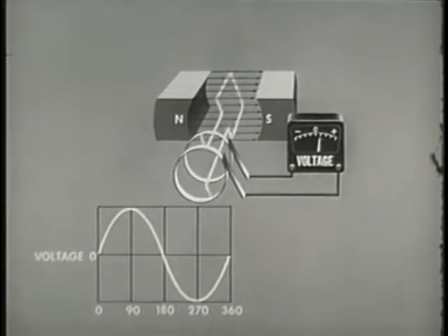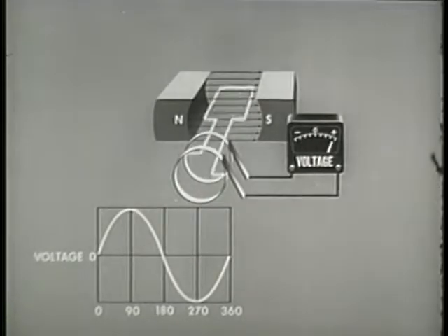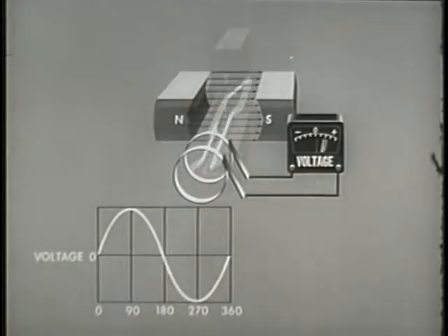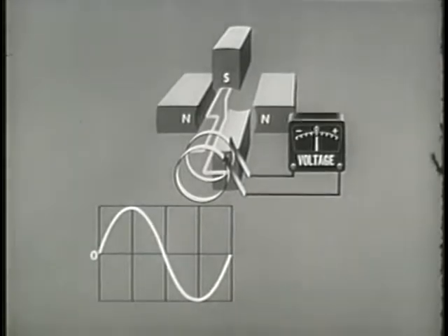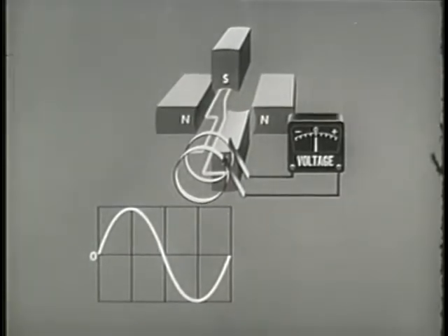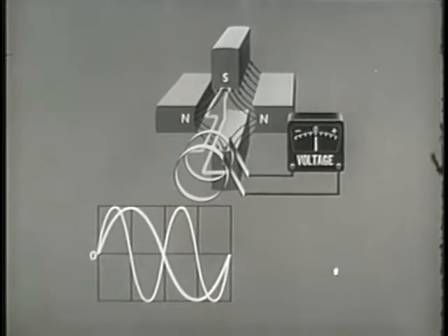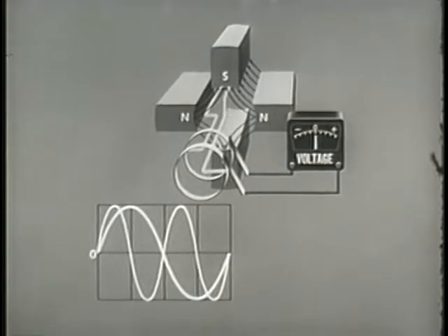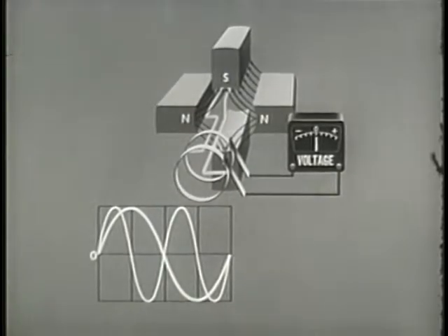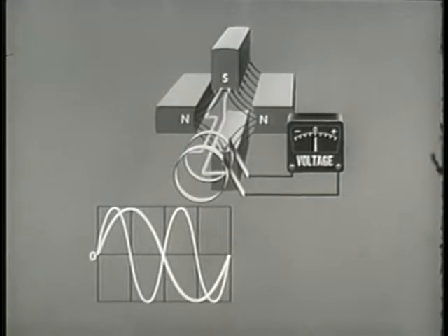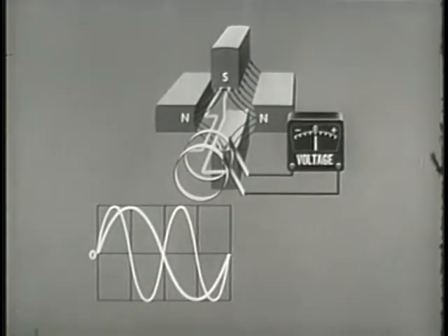In this example, the two-pole machine used has one magnetic field. As the armature makes one revolution, one magnetic field is traversed. Adding another pair of poles adds another magnetic field. Now there are two magnetic fields. The armature moves through one field in half a revolution. In one complete revolution of 360 mechanical degrees, the armature passes through two fields equal to 720 electrical degrees, and two cycles of AC are generated. Frequency can be changed in the AC generator by the introduction of additional magnetic fields.